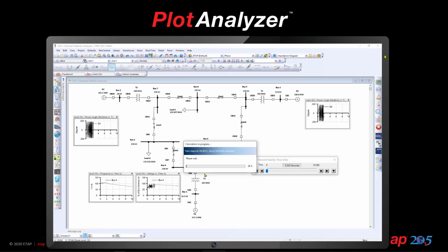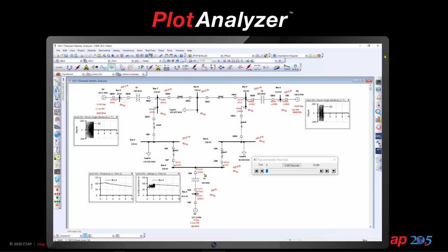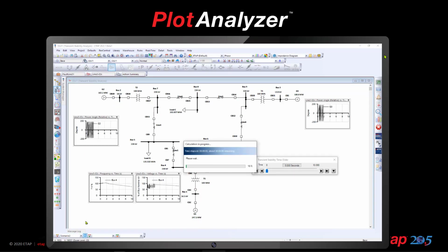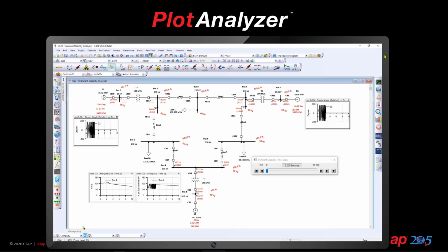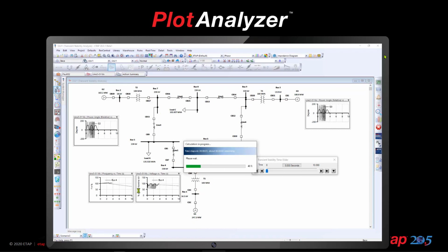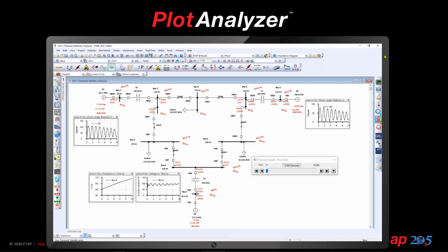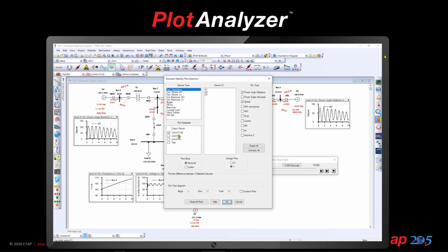But the true power of the plot analyzer comes into the picture when you are running more than one scenario inside the program and generating different results. In this case, we can see different results being displayed on the plot view, which is our live view that's directly embedded onto the one-line diagram. We're essentially looking at the generator relative angles when we change our fault clearing times to determine the critical fault clearing time for this system.